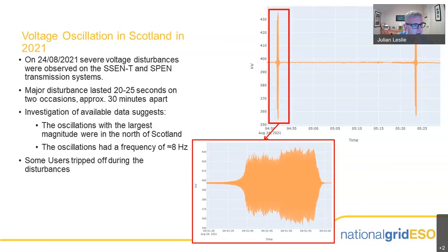Initially, obviously, we weren't sure what the root cause was. So we took some very short-term actions and gave advice into the control room to run a bit more rotating plant. There are some hydro machines in Scotland that were off for maintenance at the time, so as they've come back, we've said, if there's 5 or 6 of these machines, we need to be running 3 out of the 6 to make that happen. That's running, and we've done that since August, and it seems to have calmed the network down. We've not seen the oscillations since.